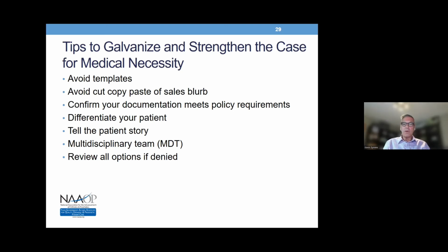A couple of last points that I think are really worth bearing in mind. If you're replacing an existing prosthesis for a patient with the same or similar, perhaps because the device is simply beyond economical repair, and you're just going with the same basic design or a repeat, then you will still need physician documentation. You will still need good documentation on your own behalf, but you might not necessarily need to spread that net too far. That's your call, of course.